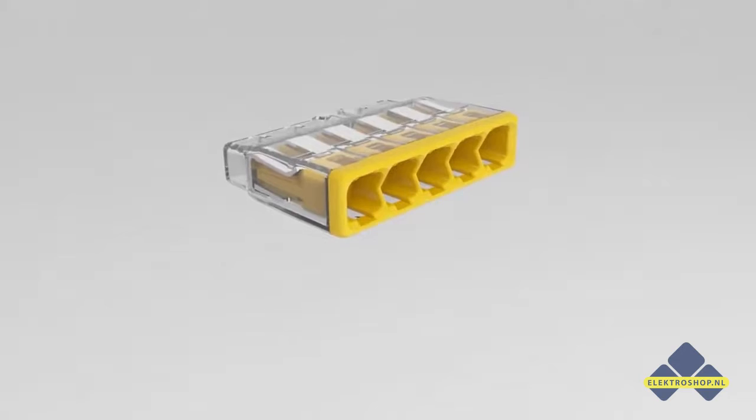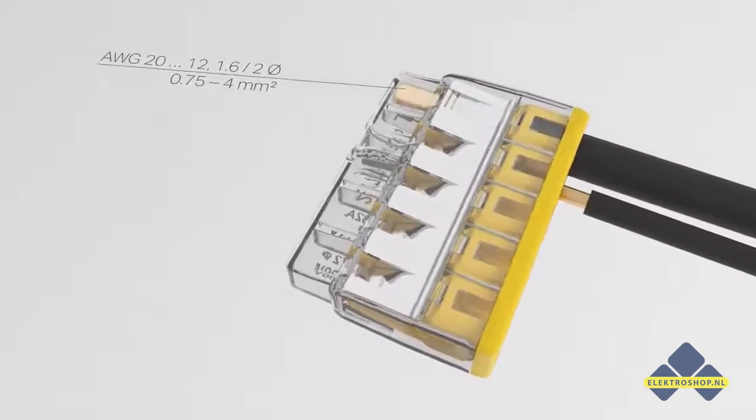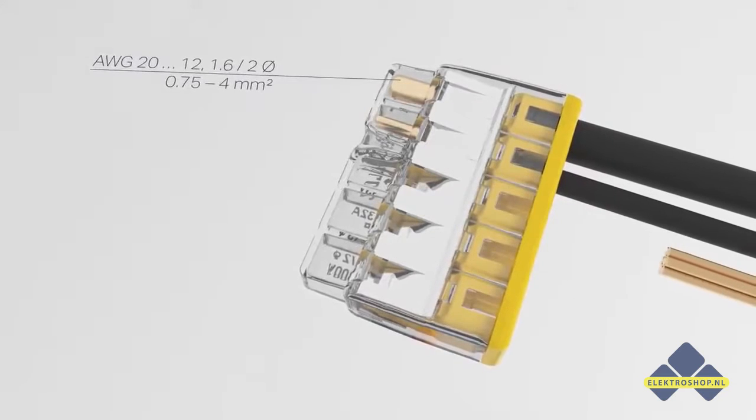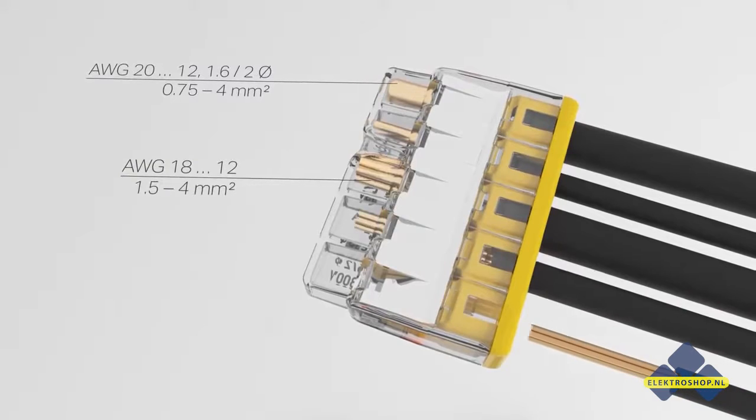Solid conductors with cross sections ranging from 0.75 mm² to 4 mm² and stranded conductors from 1.5 mm² to 4 mm² can be reliably connected just by pushing them in.